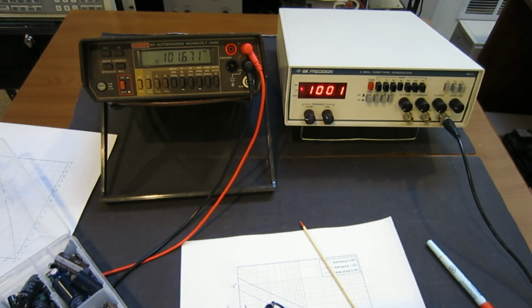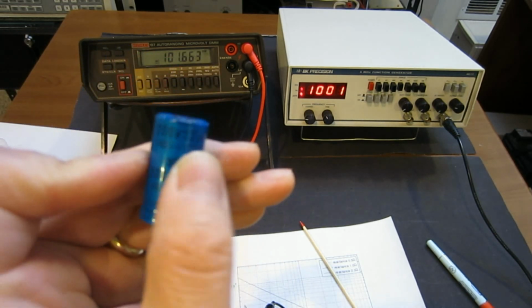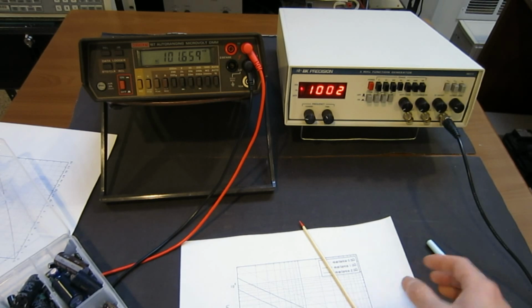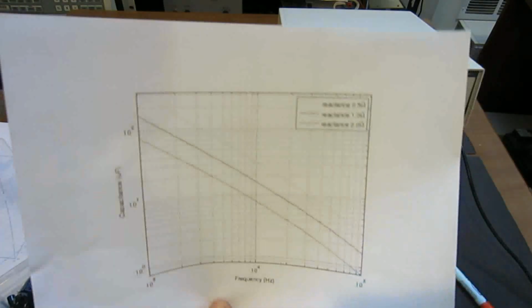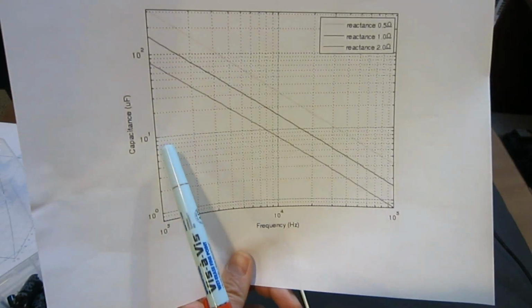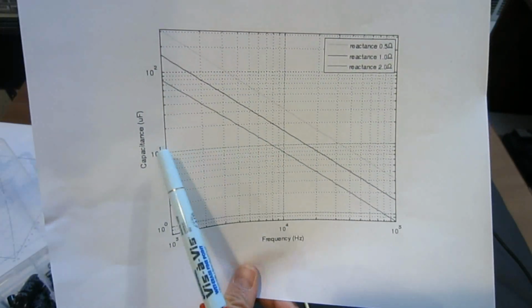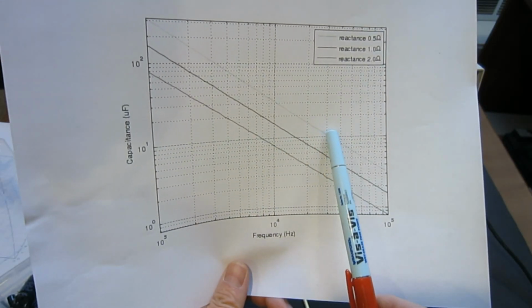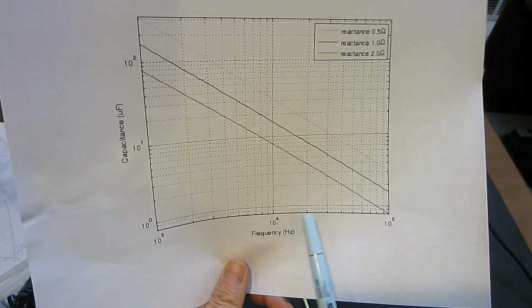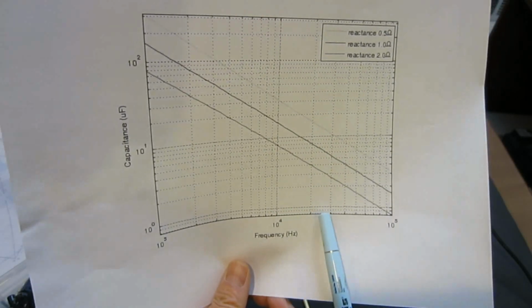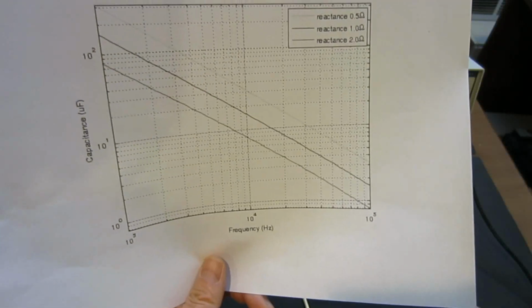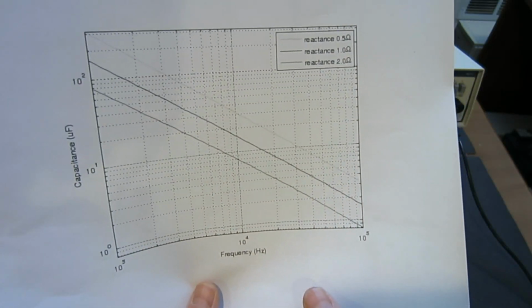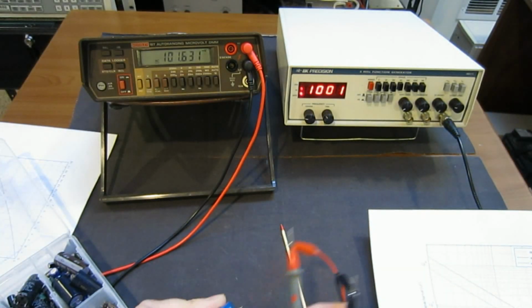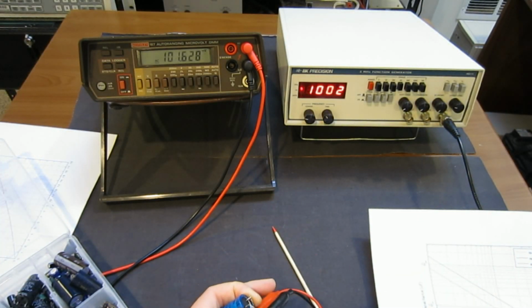If we are measuring something that is lower in capacitance value, for instance this one, which is 22 microfarad, then you cannot use this 1 kilohertz frequency because that will be too low. Remember, we saw in this diagram that for 10 microfarad, we probably need at least 30 kilohertz in order for us to be able to ignore the reactance. So let's first try without increasing the frequency. We'll see what it looks like.